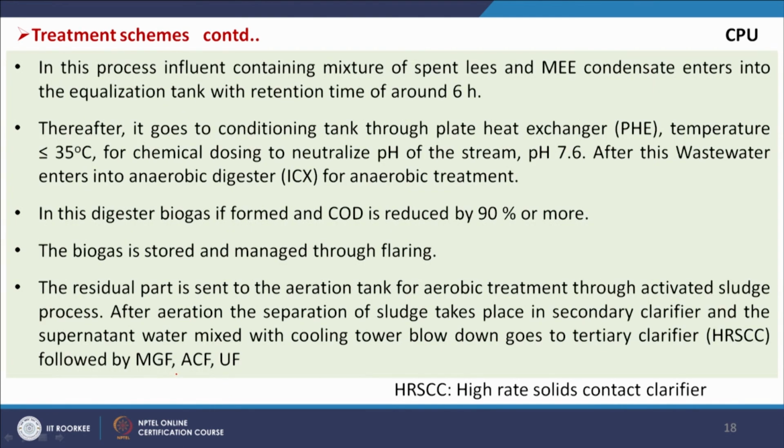And in this process in CPU, influent containing a mixture of spent lees and MEE condensate enters into the equalization tank with a retention time of around 6 hours. Then it goes to the conditioning tank through a plate heat exchanger, at a temperature less than 35 degree centigrade, for chemical dosing to neutralize the pH of the stream, pH 7.6, and after this wastewater enters into the anaerobic digester for anaerobic treatment.